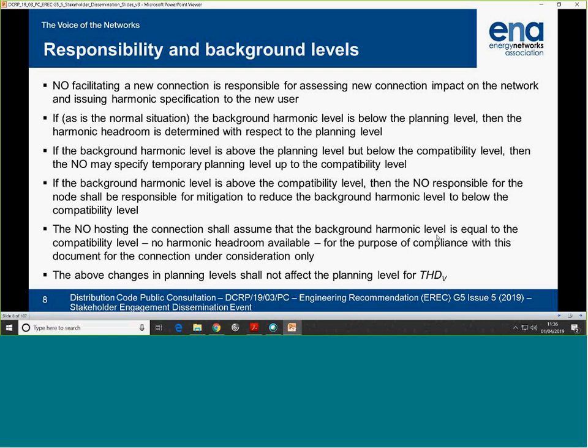Assessment of that particular connection in hand, they have to consider, according to the guidance in this domain, compatibility of planning level as the background. There is no harmonic headroom available for this connection. The harmonic headroom is 0. All these planning levels or assumed background equal to compatibility level shouldn't affect the THD. It has to be below the level in the plan tables. Any questions so far?